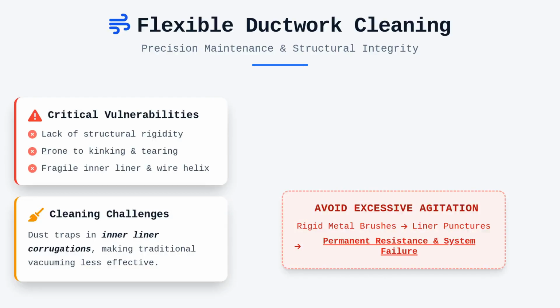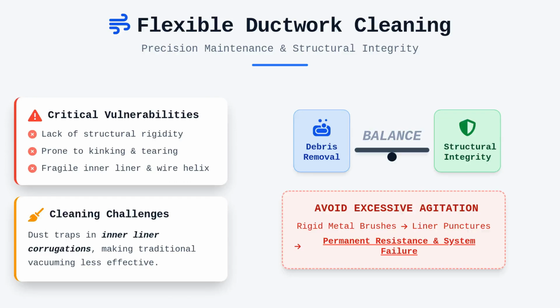Furthermore, flexible ducts often accumulate dust in the corrugations of their inner liner, making traditional vacuuming less effective. You have to balance the need for thorough debris removal with the necessity of maintaining the structural integrity of the flexible connection.